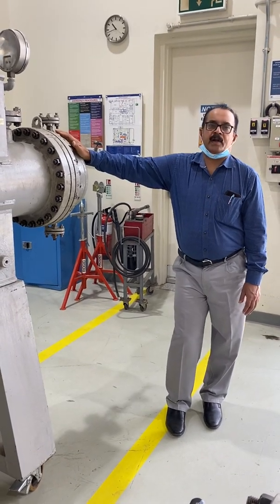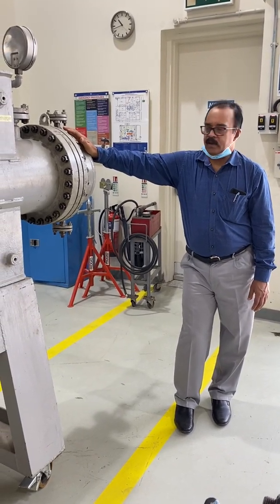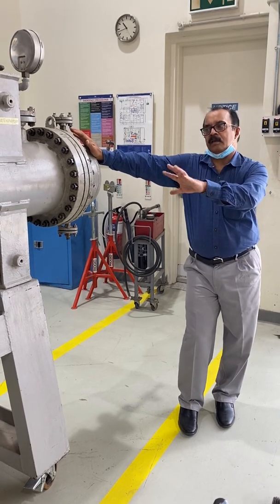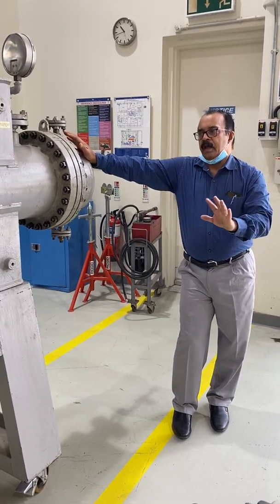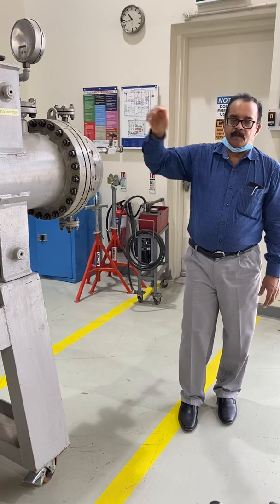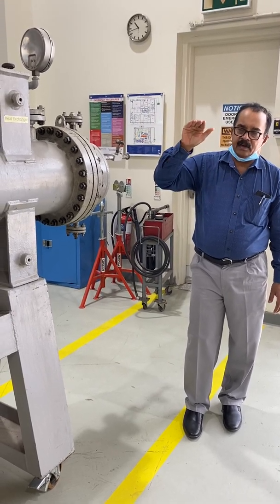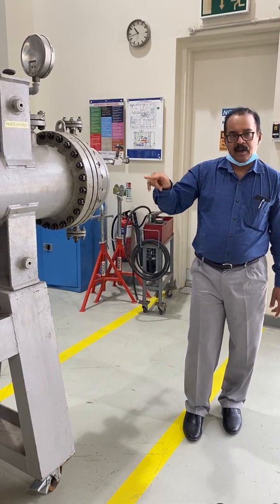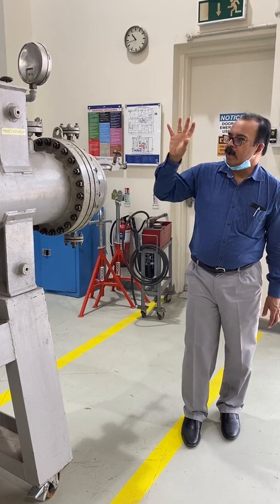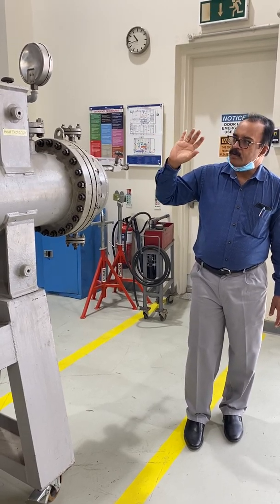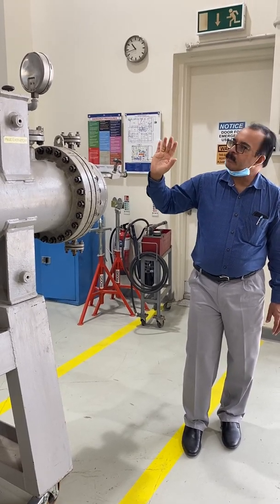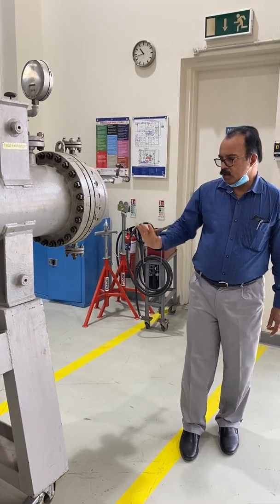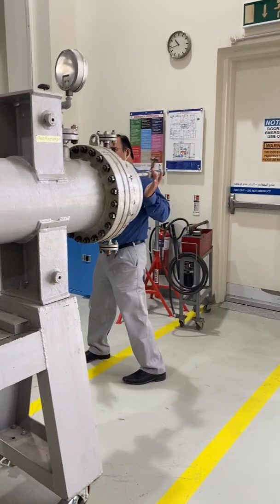When you do the hydro test, you must wait a minimum of 30 minutes. After pressurizing the heat exchanger, wait for 30 minutes and check the pressure gauge. If the gauge shows a drop in pressure, it means there is a leak, and you must rectify it. If there is no drop in pressure, the heat exchanger is ready for use. That is about the heat exchanger.